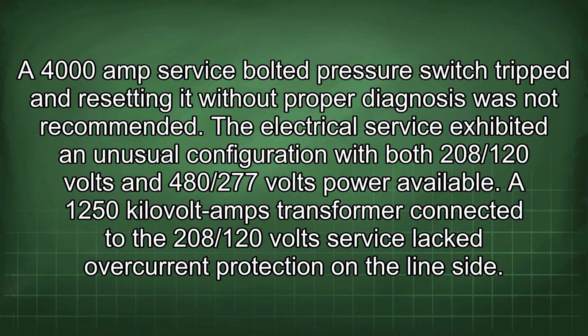A 4000 amp service bolted pressure switch tripped, and resetting it without proper diagnosis was not recommended. The electrical service exhibited an unusual configuration with both 208/120 volts and 480/277 volts power available. A 1250 kVA transformer connected to the 208/120 volt service lacked overcurrent protection on the line side.